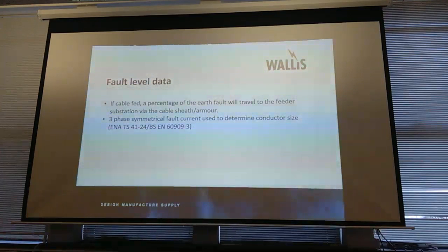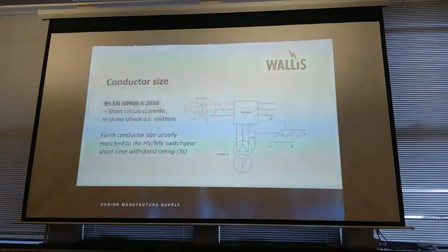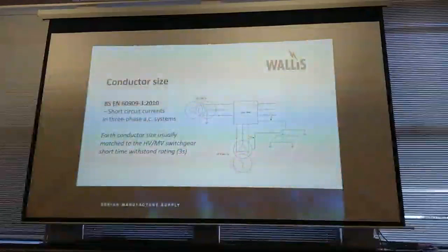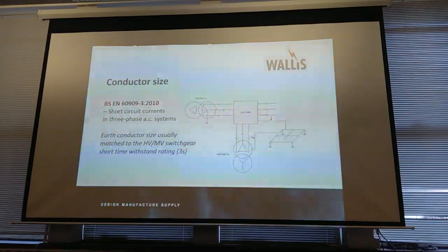We asked for the 3-phase symmetrical fault level when we're doing the designs, because that's what we tend to size the conductor to. So to determine whether we're putting 25 by 3 copper in the ground or 50 by 6 or whatever, we tend to rate it to 3-phase symmetrical. And I have got a little drawing, and forgive my crude sketches. Under IEC, like BS EN 60909-3, which talks about simultaneous but independent faults to Earth, it's saying if you've got an RMU, for instance, that faults phase 3 to Earth, and you've got a transformer that faults phase 1 to Earth, and it's sharing the same Earth system, as you do in a little distribution substation sometimes, you can actually get a phase-to-phase fault through the Earth system. So that would be the reason you would size the copper to the 3-phase symmetrical.